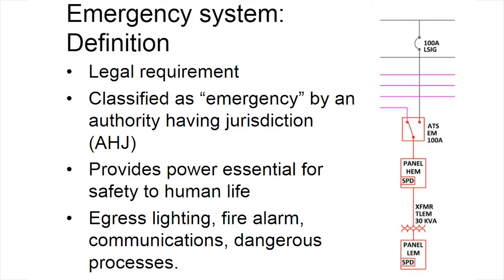So of the three types of standby systems, the emergency system has the highest priority. Its purpose is mostly protecting people's lives. Here's a snippet of the one-line diagram on the right, enlarged a little bit, showing the normal and standby feeds, the automatic transfer switch, and two levels of distribution. So emergency systems, by definition, are required by law or by a code or by an AHJ, and they are specifically classed by that statutory authority as emergency systems. They provide power that's essential for human life.